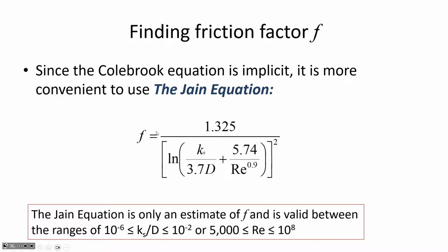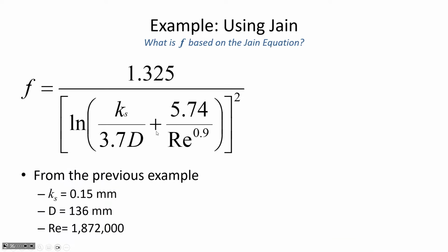Like we could use the Manning's equation to calculate head loss due to pipe friction through an enclosed pipe, but it's not accurate for closed conduit flow. There is the Hazen-Williams equation, which is convenient, but it's less accurate. So the Darcy-Weisbach equation is the most accurate, because it's adaptive to the flow conditions. The f value, the way that you estimate friction, is sensitive to flow conditions. And a lot of the other methods aren't.